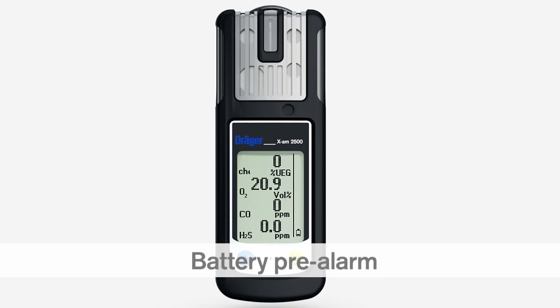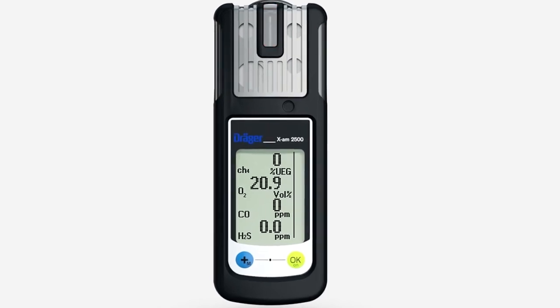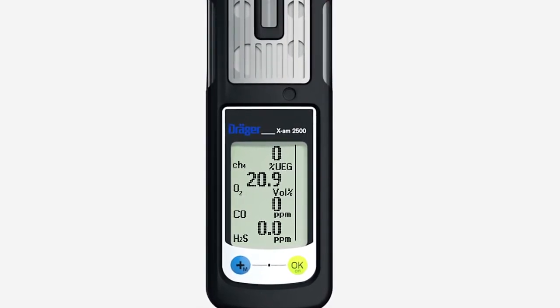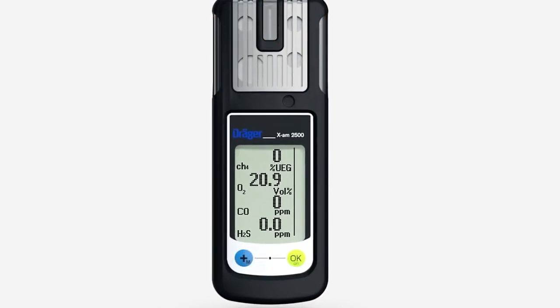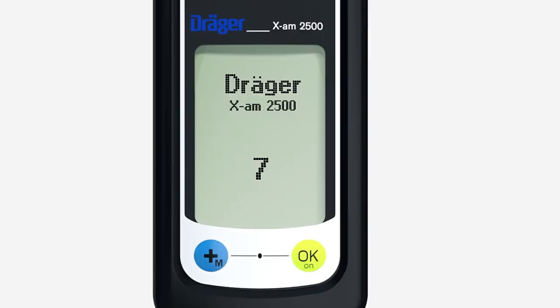If the battery of your X-am 2500 will only last for another 20 minutes or so, the battery pre-alarm is activated. The audible, visual and vibration alarms are activated periodically. The battery symbol flashes at the bottom right. You can acknowledge the alarm by pressing the OK key. The main battery alarm, indicating that the battery is about to run flat, is signalled by the audible, visual and vibration alarms. A countdown in the display counts down from 10, after which the device switches itself off.